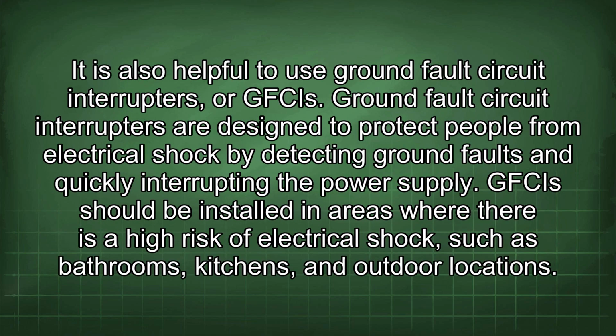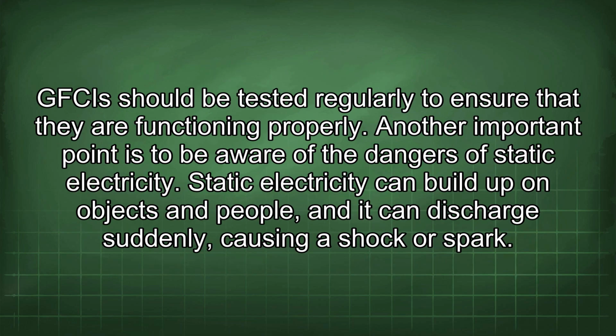It is also helpful to use ground fault circuit interrupters, or GFCIs. Ground fault circuit interrupters are designed to protect people from electrical shock by detecting ground faults and quickly interrupting the power supply. GFCIs should be installed in areas where there is a high risk of electrical shock, such as bathrooms, kitchens, and outdoor locations. GFCIs should be tested regularly to ensure that they are functioning properly.